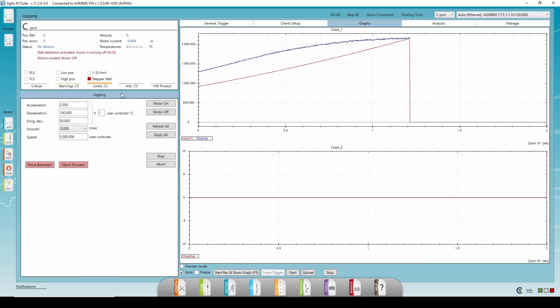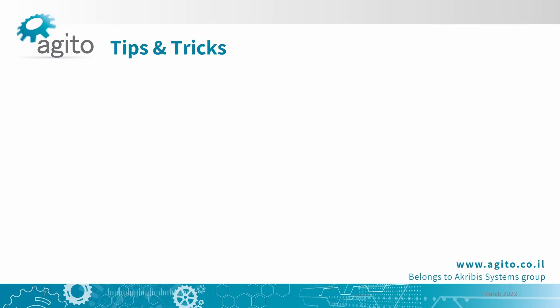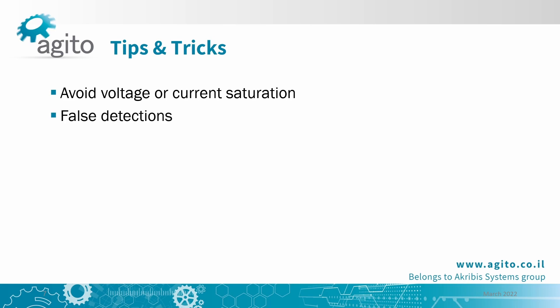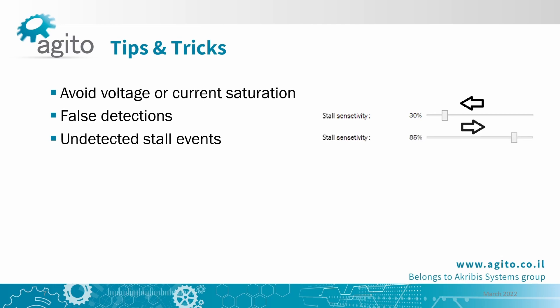To help you with your setup of the feature, in case you will encounter any problem, let's go over some tips and tricks. During calibration, make sure your motor avoids voltage or current saturation, because it will lower the threshold unnecessarily. If you get a lot of false detections, lower the stall threshold. If you don't get stall detection at values you are certain the software should detect, raise the stall threshold.